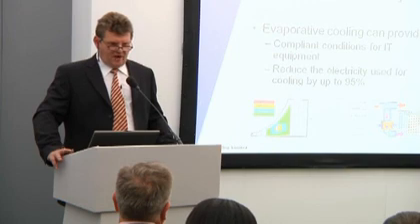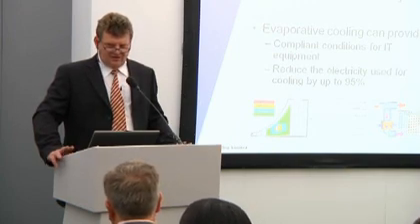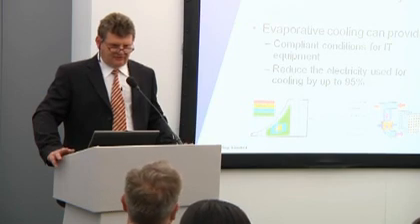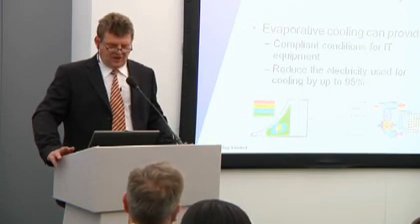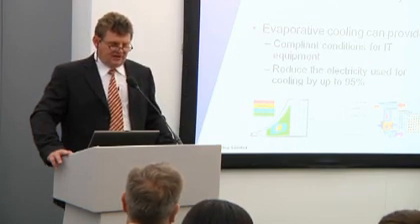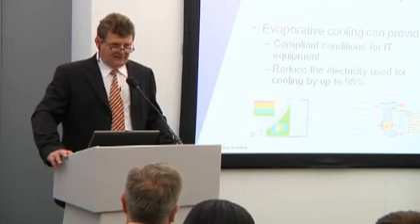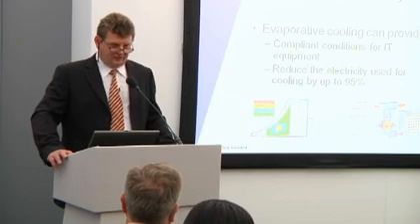If you embrace that widening of those operating standards, then you can implement a ventilation scheme based on these principles and reduce your energy bill of your cooling by over 90%. Now, in most cases, that means that you can reduce the energy usage of your data center by a half, with a capital investment which could pay for itself in under a year.